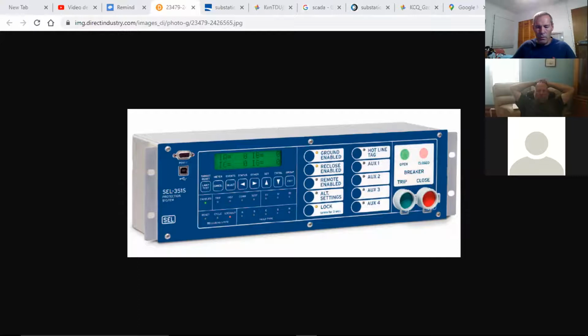In local, you can do anything with the control, but it is still SCADA monitored. Essentially, you put this thing into local, you've taken away control from your dispatchers in the control center, and you can do things on the panel that you need to do. But SCADA, the guys in the dispatch center, are still able to see what's happening. In remote, you can open only.